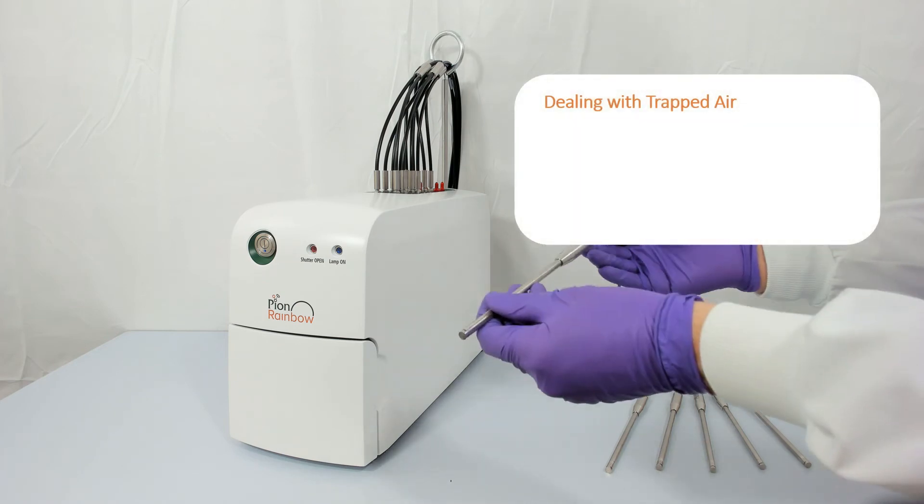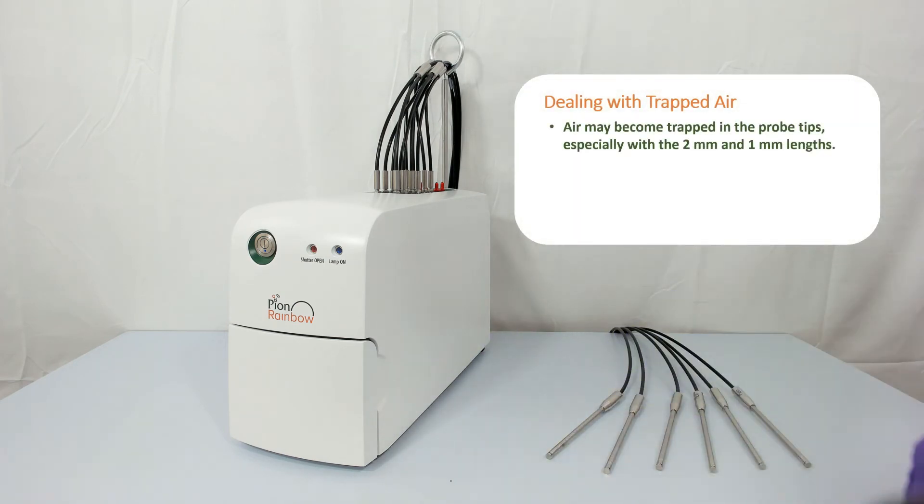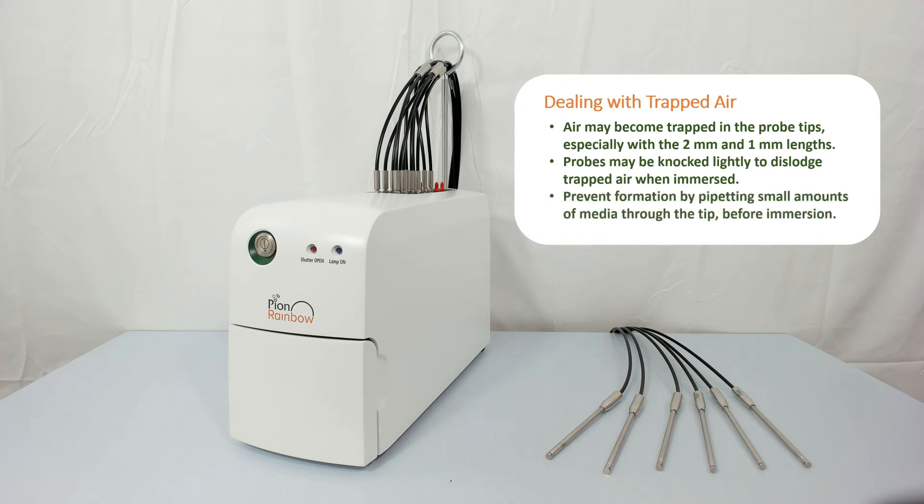As the path length reduces, the likelihood of air bubbles becoming entrapped in the path becomes greater, especially so with the 2 and 1 mm tips. Bubbles may be removed from the path either by knocking the probes lightly, or their formation may be discouraged by rinsing the probe tip with a small amount of the medium prior to immersion, in order to break the surface tension between air inside the tip and the medium. Using degassed media is also advisable.